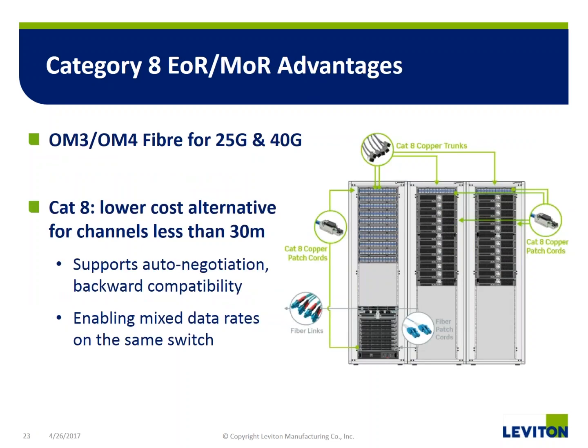In the end of row, middle of row advantages, you're really looking at OM3, OM4 fiber. Cat 8 is going to be the lower cost alternative for channels less than 30 meters. We talked about the advantage of auto negotiation and backwards compatibility - this provides mixed data rates on the same switch. One of the key advantages of this is the ability to stagger your upgrade migration.